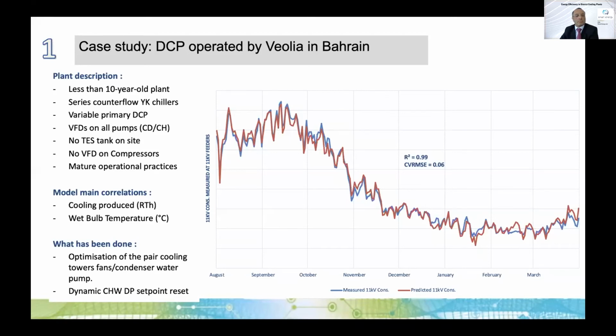What's quite important to mention here is that the site's got a fairly mature operations team with a lot of effort already put into looking for ways to increase efficiency. We've deployed an IPMVP type method to validate the savings generated by the solution, which is the model you can see on the right of the screen. And we've implemented 2 of the modules that we've talked about before, the optimization of the heat rejection side and the dynamic chilled water DP set point reset. We didn't look into plant sequencing because, since this is variable primary only, the sequencing didn't have much impact.